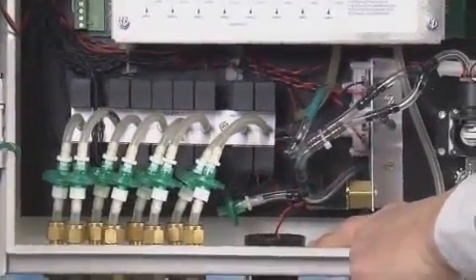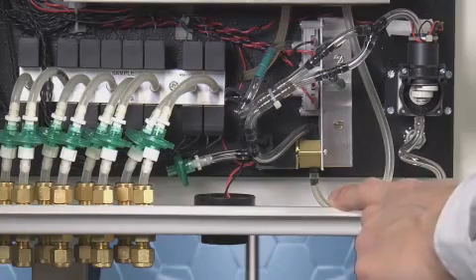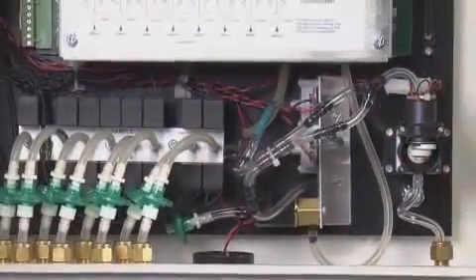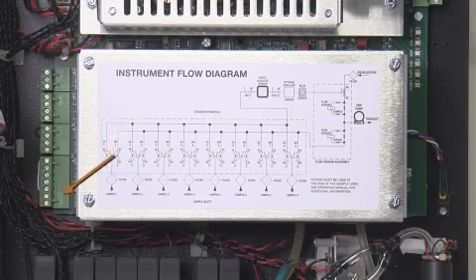Another feature is an 85 decibel horn located at the bottom of the product. It's very loud and will certainly get your attention even in a loud mechanical equipment room. Also in this product we have four relays which allow a customer to set up for three levels of alarm: caution, warning, and a major alarm, as well as a fault. Another output is a 4 to 20 milliamp output, and you can also have a 0 to 10 volt output, which is useful for going back to control systems to get information on product functionality without having to actually go to the instrument itself.